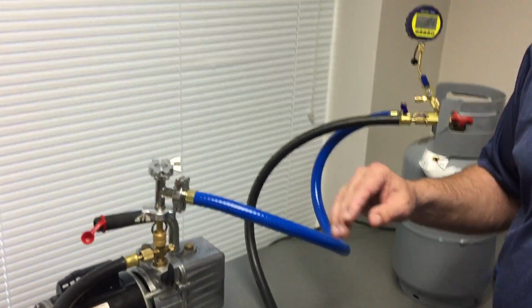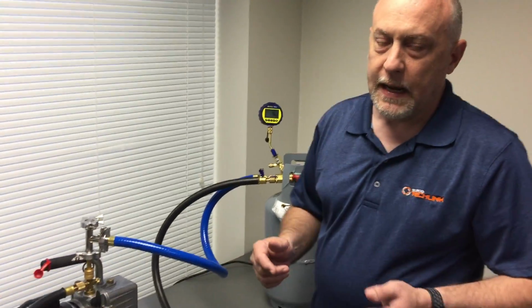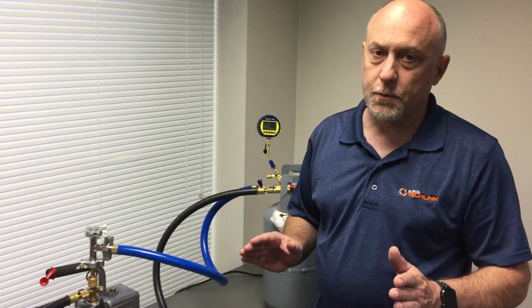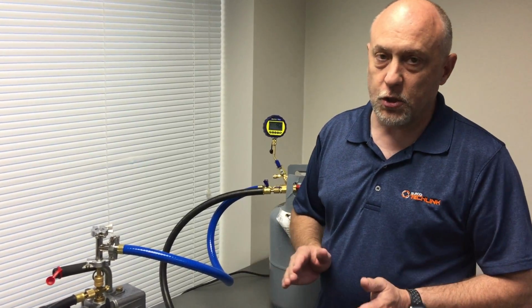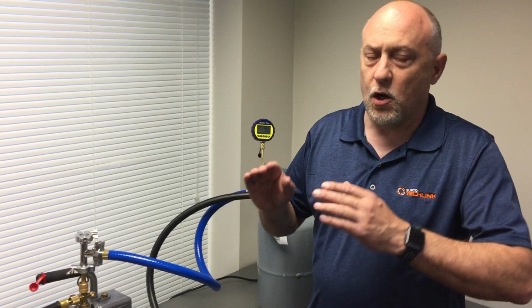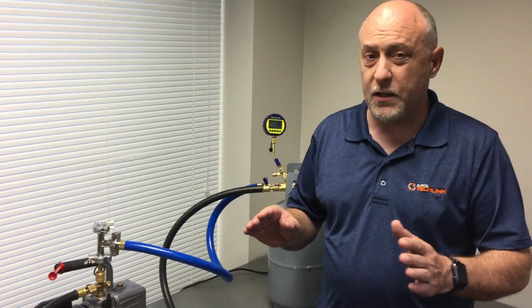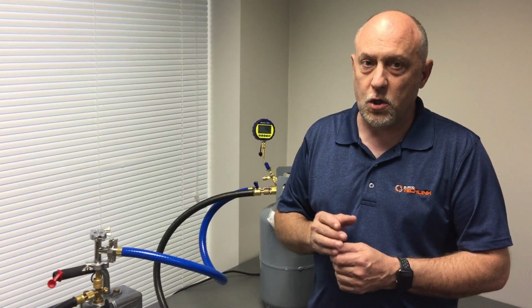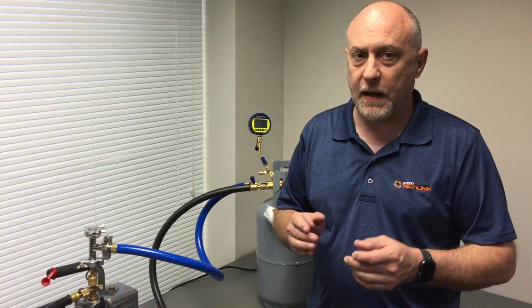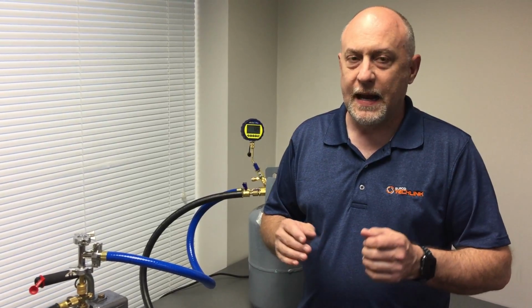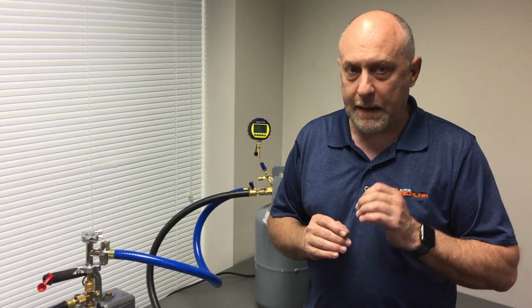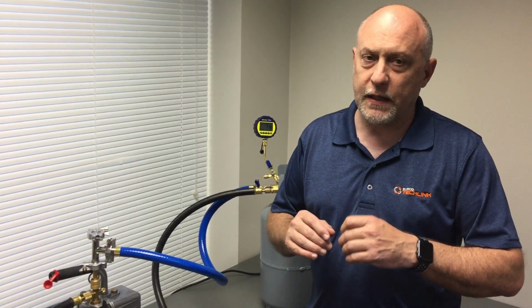So you can see right here, just introducing a competitive hose in here, how it ultimately erodes the vacuum of the system. And if you want to get the true performance out of TruBlu hoses, then just use TruBlu hoses in the equation. Now, it's not that that hose is going to dramatically undermine the effect of it, but here's where it falls out. We're losing somewhere between 50 and 100 microns in that evacuation, and that is critical to dehydration, right? We want to get all the moisture out of the system. And if we're tied in with a competitive hose in there, you're just not getting the full advantage of the non-permeable hoses that TruBlu is made from.